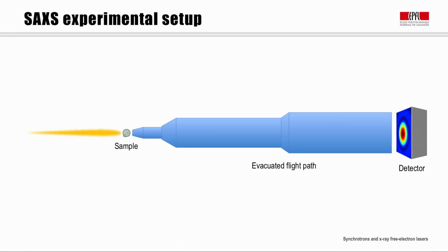It's important to avoid spurious signal arising from other elements at the beamline, such as forward scattering from X-ray windows or indeed air. So, for example, the path between the sample and the detector is normally evacuated using a long flight tube as shown here, while the entrance window to that flight tube is typically fabricated not from amorphous material such as Kapton, which would produce its own SAXS signal, but from thin sheets of highly crystalline material, such as diamond or mica.